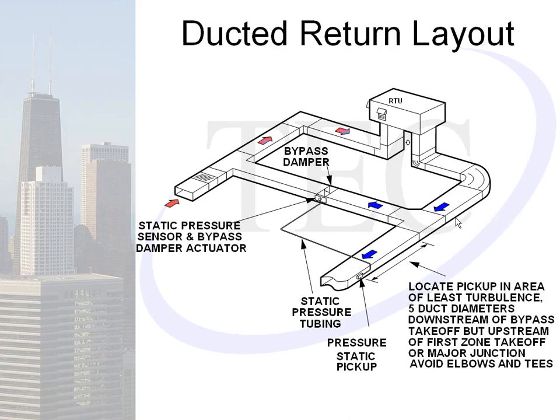We want to avoid the temptation to install the bypass duct between the supply and return drops, as that will prevent supply air from mixing properly with return air and cause hot and cold pockets across the evaporator coil and heat exchanger. Off the supply, we want aerodynamic fittings, and then downstream of the first or second bend, place the T with the bypass duct. The pressure pickup location is critical — after the bypass branch but before the first takeoff, approximately two-thirds of the way down the duct, avoiding locations with a lot of turbulence.